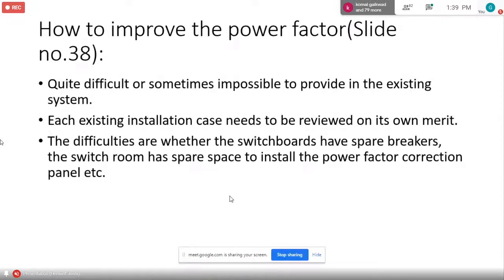Quite difficult or sometimes impossible to provide in an existing system. Each existing installation case needs to be reviewed on its own merit, whether you can install or not. Some installations you just cannot. The difficulties are whether the switchboard has spare breakers and the switch room has spare space to install the power factor correction panel, etc.